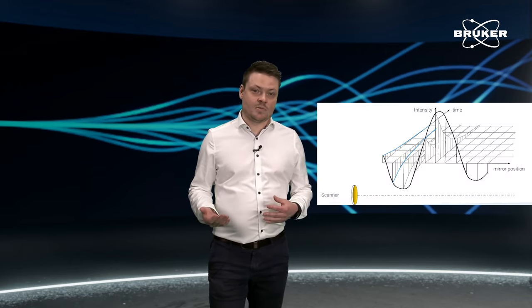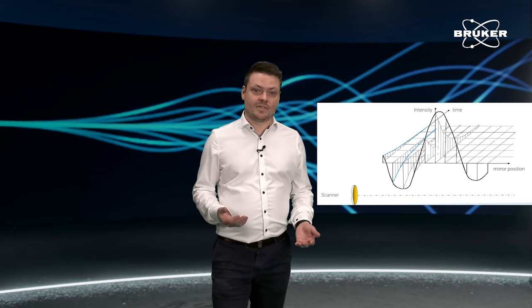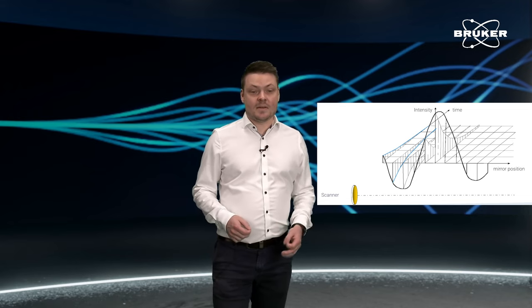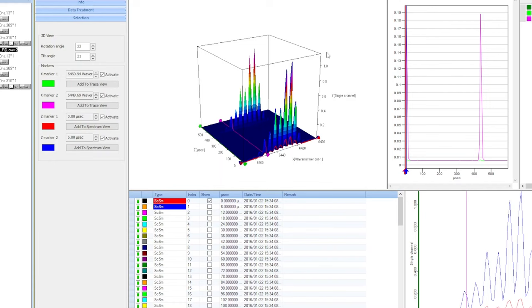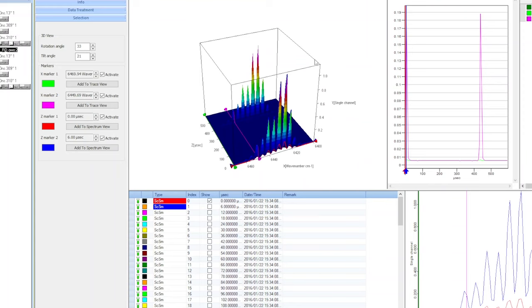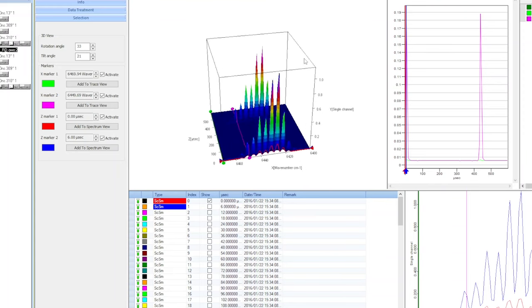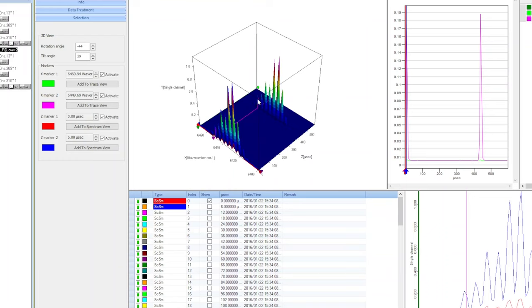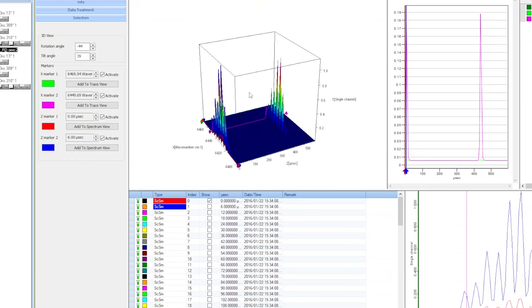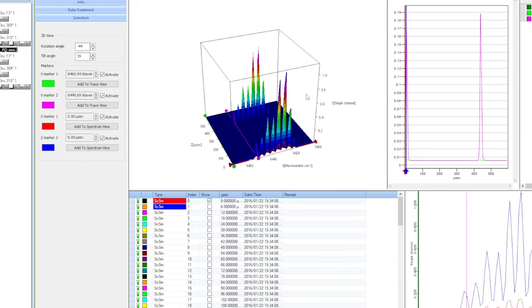The stable background conditions come into play when you want to perform long measurements. This could be, for example, step-scan measurements that can last for several hours. Step-scan measurements give you a very high spectral resolution and also a very high time resolution. This can be used to characterize laser sources. The high resolution in the spectral and in the time domain allows you to analyze the shape and the length of single laser pulses.